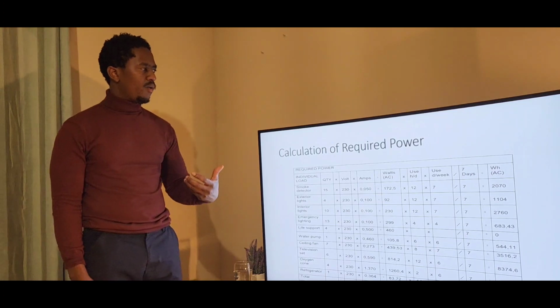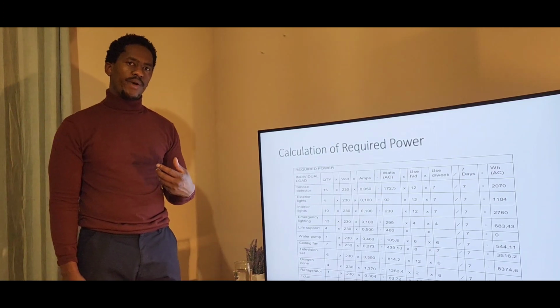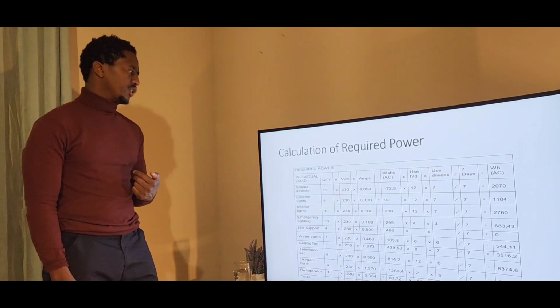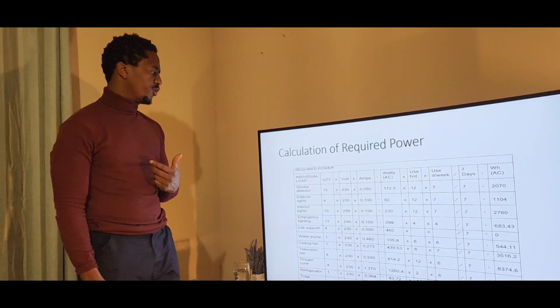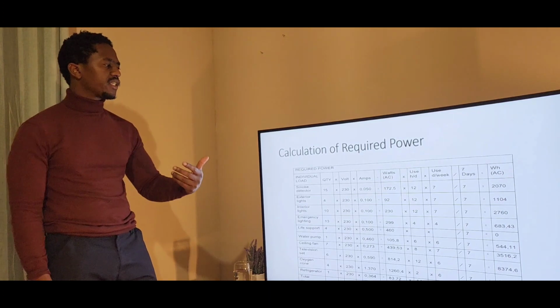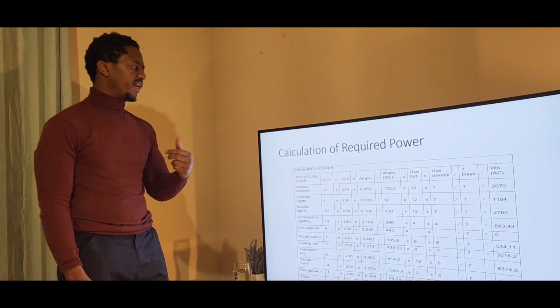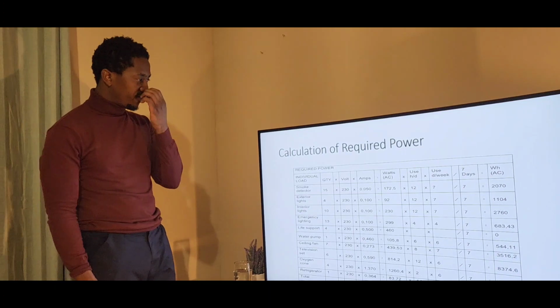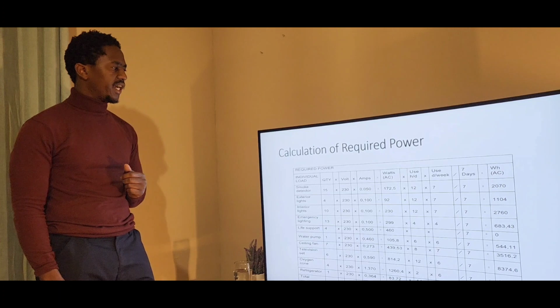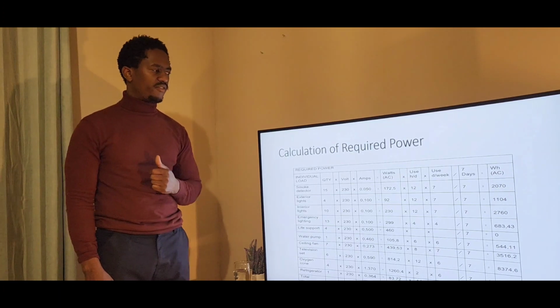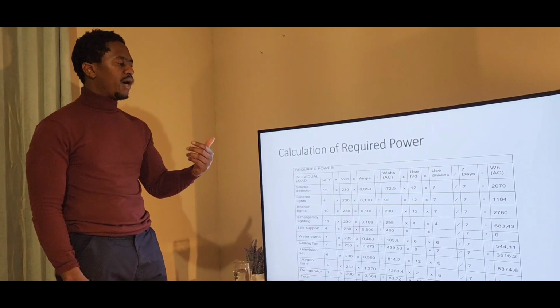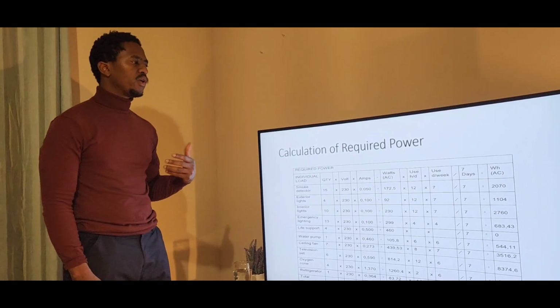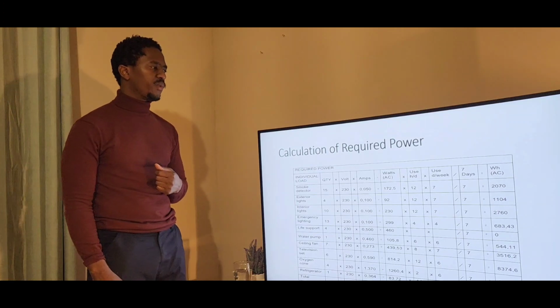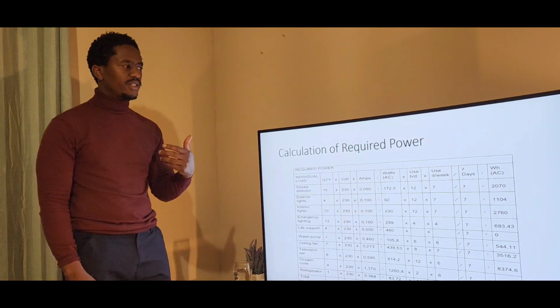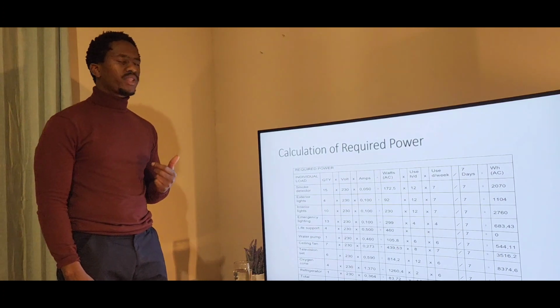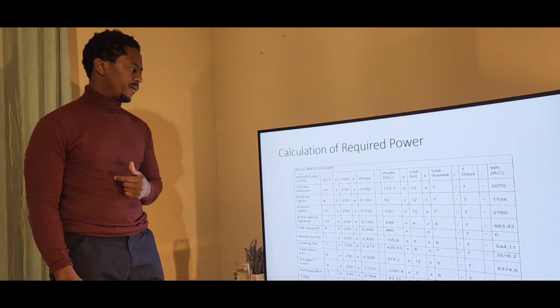This is the required power calculations that were used when designing the system. We can make an example with the smoke detector. It takes 0.050 amperes, the nominal voltage is 230, and the quantity is 15. So the wattage of the smoke detector is 172.5 watts. We multiply that by the hours in a day it is used, which is 12 hours, and by the days used in a week, which is 7 days. We get 2070 watt hours.